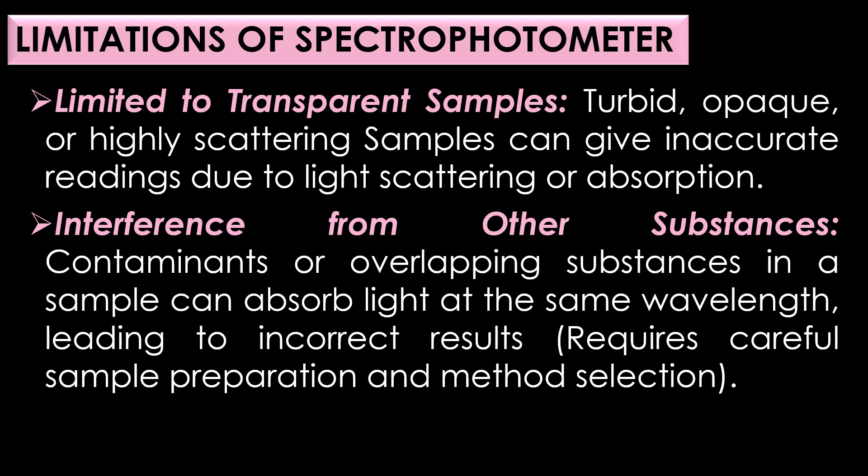Limitations of spectrophotometer. The first limitation is limited to transparent samples — spectrophotometers are primarily effective for transparent or translucent samples. Turbid or highly scattered samples like suspensions or emulsions can give inaccurate readings due to light scattering or absorption. The second limitation is interference from other substances — contaminants or overlapping substances in a sample can absorb light at the same wavelength, leading to incorrect results, requiring careful sample preparation and method selection.